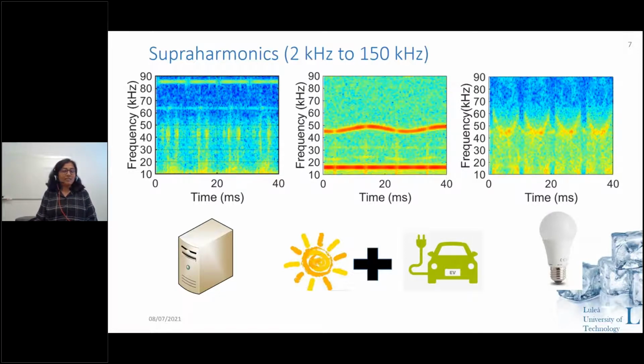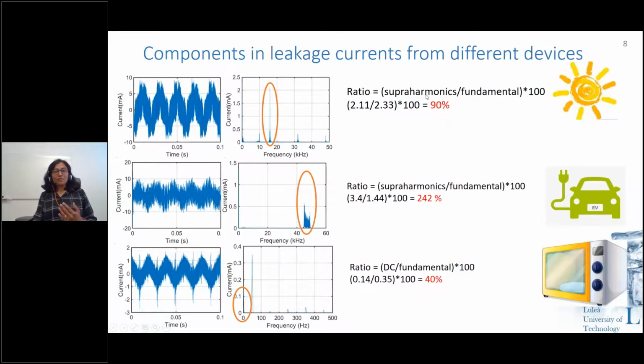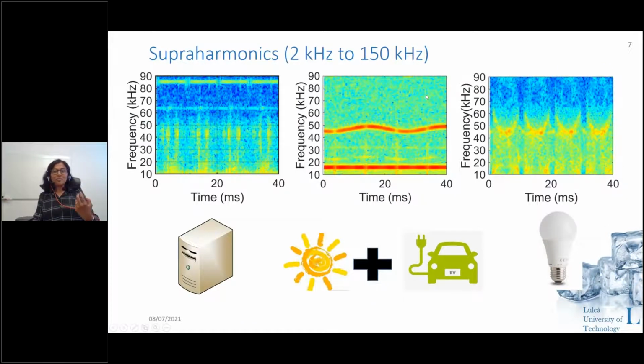But how is it normally dealt with? How do we protect the grid against the emissions? Usually all devices have an EMI filter. The EMI filter is basically not meant to protect against supraharmonics. It should stop any frequency greater than 150 kilohertz, up to 30 megahertz, that is in the conducted emission range. But it usually has a corner frequency around 9 kilohertz, so it also gives a low impedance path. What this will do is that you will have supraharmonic emissions in the PE currents.